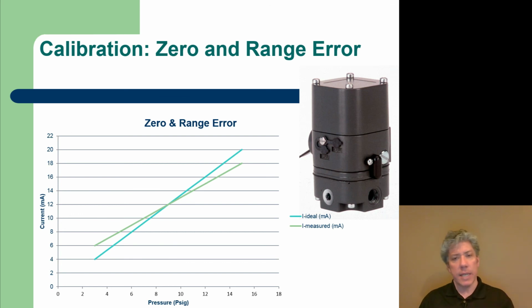Maybe the green line is the actual response. How would you change it? How would you correct it? Well, the problem is that it takes 6 milliamps to produce 3 psi, and when we give the I to P, or the current to pressure transducer, 18 milliamps, it produces 15 psi. Well, there is a range, or a slope error, or a span error, and a zero error. The entire curve needs to be shifted so that the green actual curve, the performance curve, needs to be moved to the blue ideal curve.